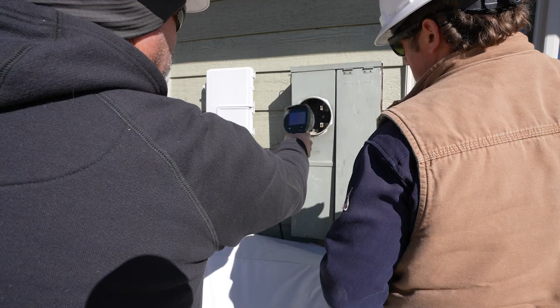With our excellent SCADA system that our SCADA team has put together, we can look and see if one of our feeders from the substation has tripped off. If it has, that gives us valuable information on where to go. If it hasn't, that's where our AMI system comes into place, and we can see where the meters are out of power on the map. With our mapping system, we can do an upstream trace, looking to find the source and which fuse actually blew.